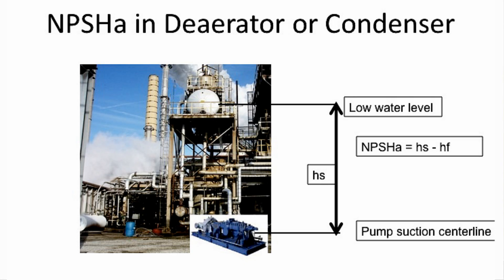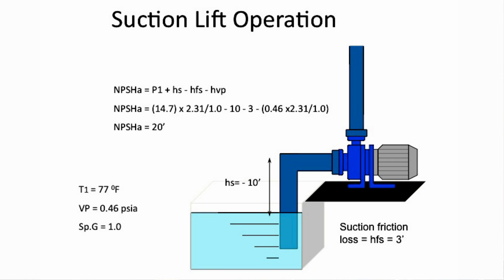Now let's look at a suction lift application. This is common when you're dewatering pits. The pit is open, so the suction pressure is atmospheric. From this, we must subtract the height of the lift — 10 feet — subtract the friction loss, which we calculated as 3 feet, and subtract the vapor pressure, and you have an NPSH of 20 feet.